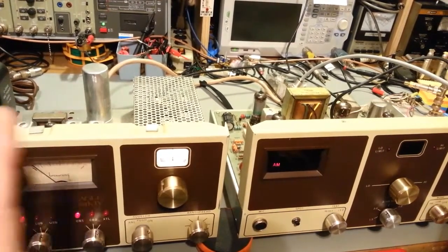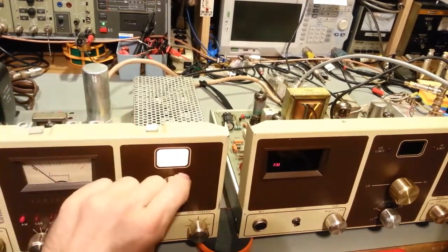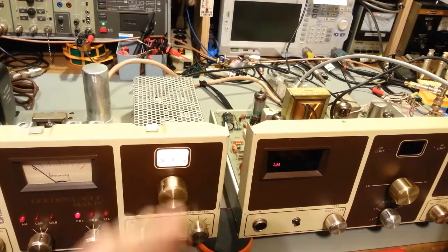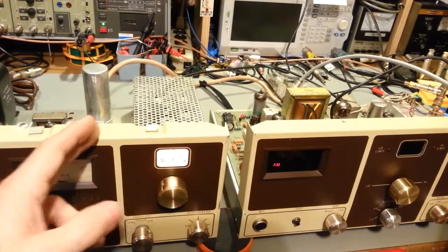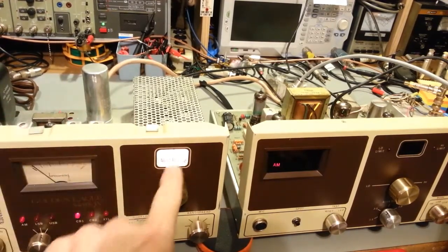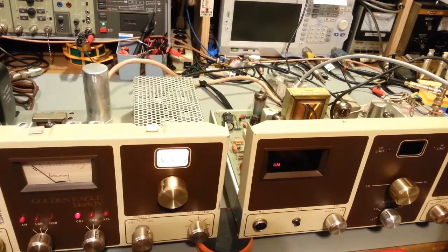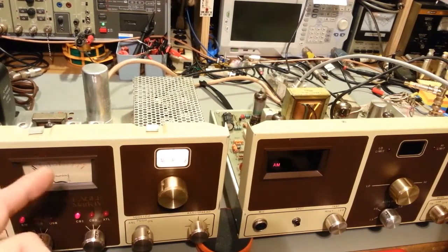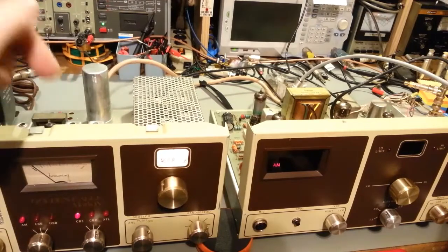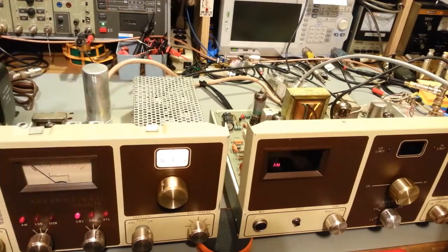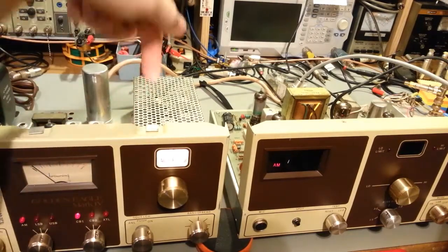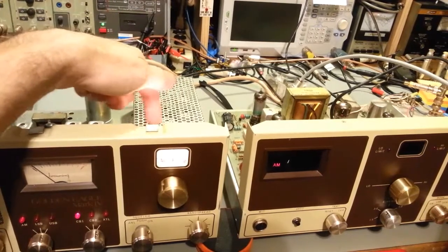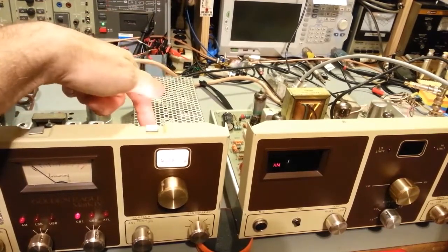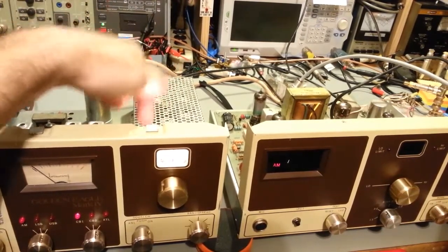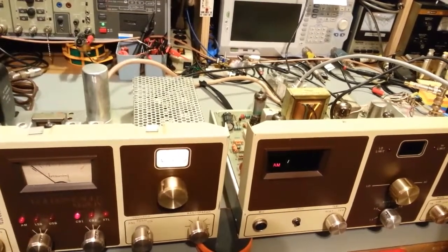Turn it back on, check it and see - is it on, is it actually off center? Because it's a very good possibility that if I install the bottom and top covers, it might actually be centered again. But check it that way. If it is off, then I'll pull the top cover, leave the bottom cover still installed, pull the top cover, and then down through the shield here you have to go down and actually through the holes in this perforated cover to do your adjustments. But this must be installed. So I need to check that.